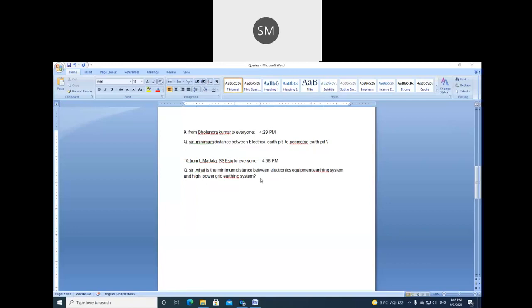It tells you what safety distance I could maintain. See, again, it is nearly the same. There is no difference. Whatever is the length of the electrode, the separation between any two electrodes has to be at least equal to the length. Equal or more than? Yeah, equal or more than, exactly. Okay, thank you.